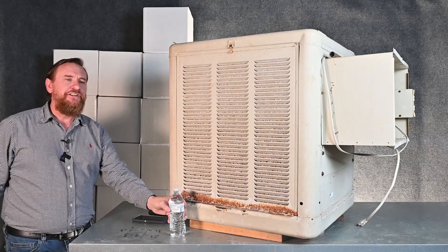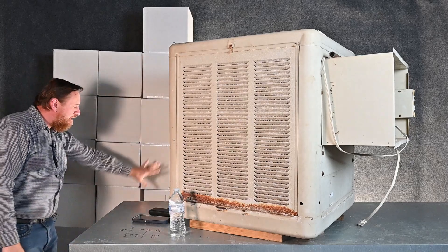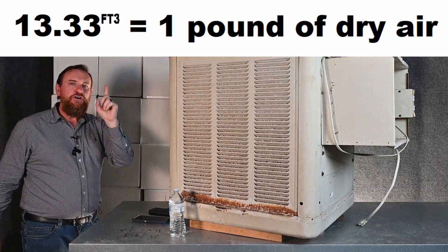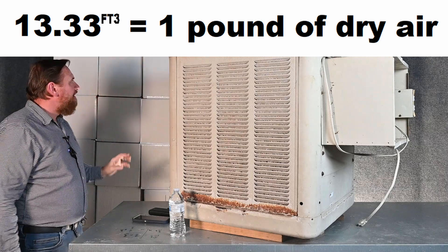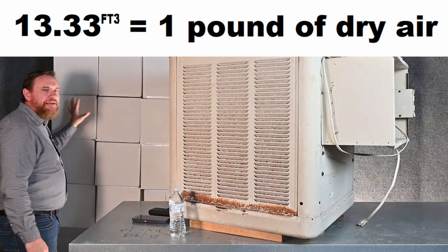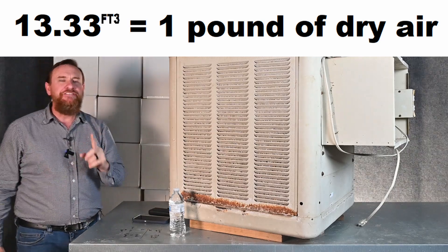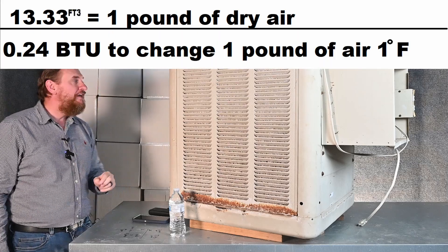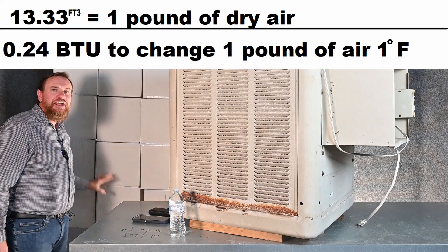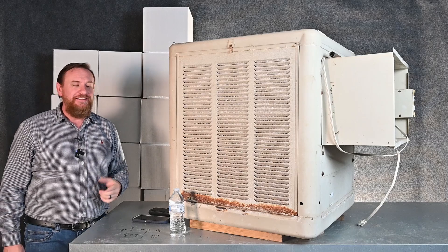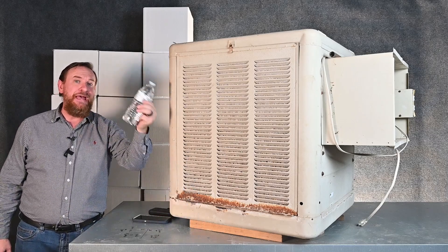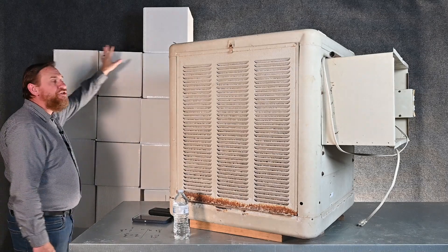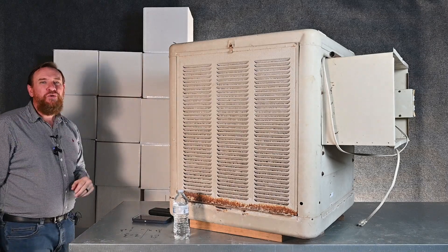Now let's look at that BTU factor. It takes 13.33 cubic feet of air to have 1 pound of air. It only takes 0.24 BTUs to change 1 pound of air 1 degree Fahrenheit. It took 1 BTU to change 1 pound of water 1 degree Fahrenheit, but it only takes a quarter of a BTU to change 1 pound of air 1 degree Fahrenheit.